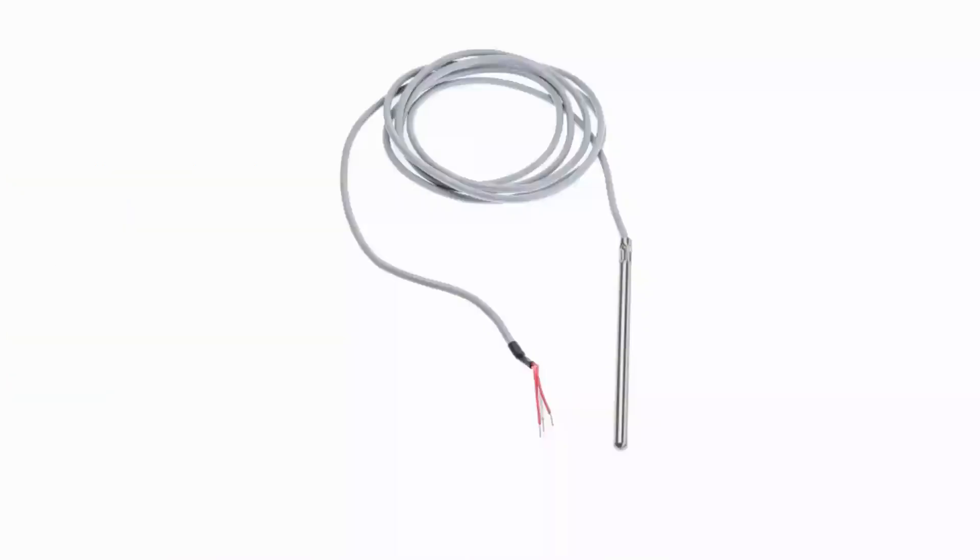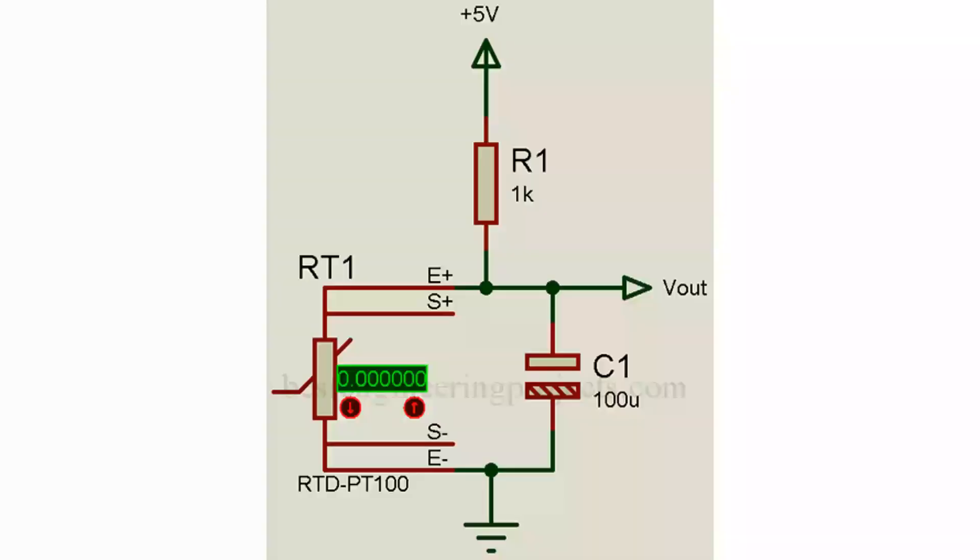Length of RTD sensor and its lead is long and might act as antenna. As a result, it starts to pick up the noise and mixes with temperature voltage. In order to avoid this problem, a capacitor of high value, say 100 microfarad, is connected parallel across RTD sensor. This capacitor acts as low-pass filter and removes almost all noise.